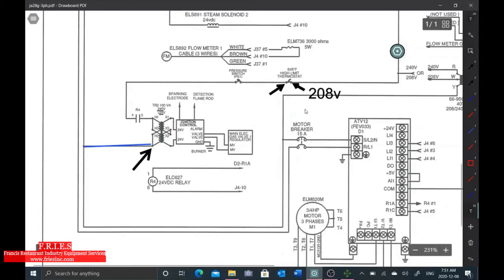And then the last test I did was test across these 2 points right here. Okay, so when I came and tested across these 2 points, now I'm testing red line to red line, potential difference, no longer going red to blue. Okay, so when we do that, it's potential difference. We're subtracting. Okay, so I got 208 volts in, 0 volts out. That's going to give me 208 volts across, which tells me this switch is in the open position.